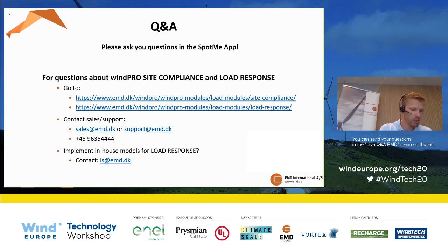Yeah, so there's a question here whether the shear calculation inside compliance, which is energy weighted, is the way according to the standard, or if it's the frequency weighted. As I understand the question, in edition 3, the text in the standard is not very clear about it, but the general interpretation was that it was the frequency weighted average, whereas in edition 4 here, it is explicit that it's the energy weighted average.